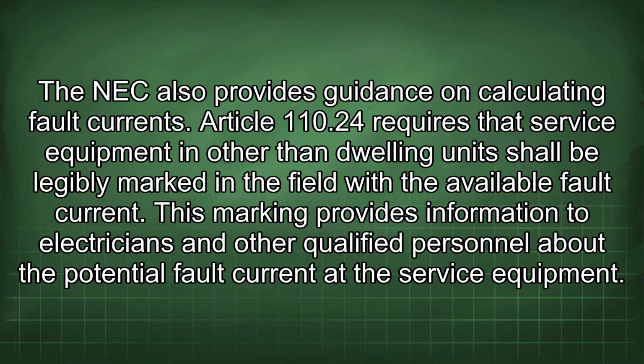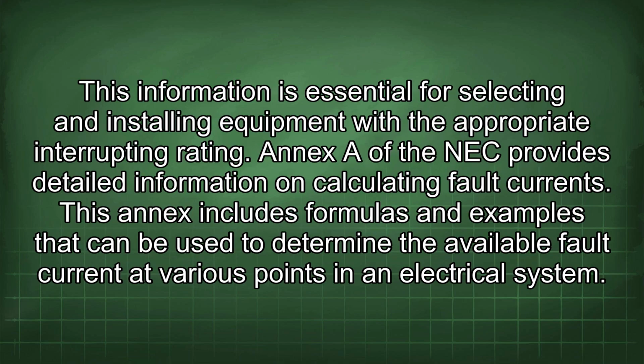The NEC also provides guidance on calculating fault currents. Article 110.24 requires that service equipment in other than dwelling units shall be legibly marked in the field with the available fault current. This marking provides information to electricians and other qualified personnel about the potential fault current at the service equipment. This information is essential for selecting and installing equipment with the appropriate interrupting rating.